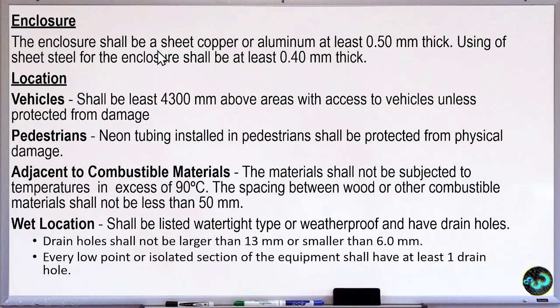Enclosure. Now, the enclosure shall be a sheet copper or aluminum at least 0.5 mm thick. Using sheet steel for enclosure, it shall be at least 0.40 mm thick. So, this is the enclosure for the controller or doon sa disconnect. So, ang minimum niya is 0.5 mm thick if the metal is made of copper or aluminum. If that is sheet steel, 0.40 mm yung kapal.